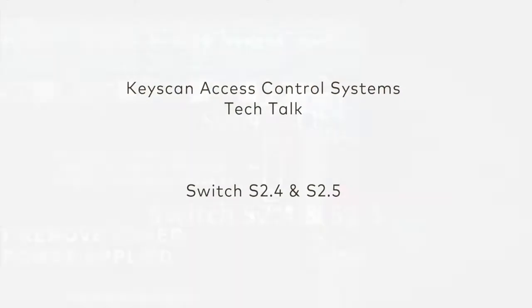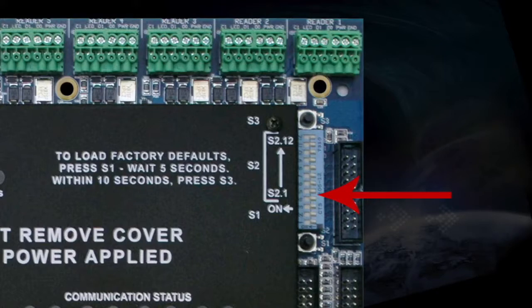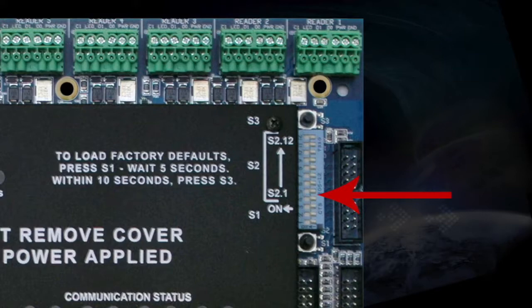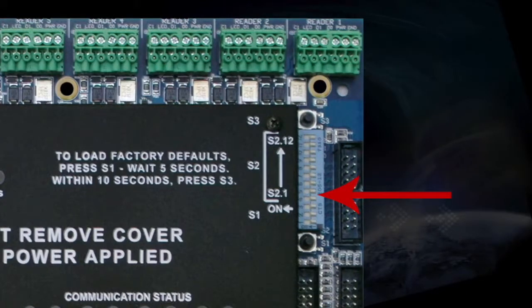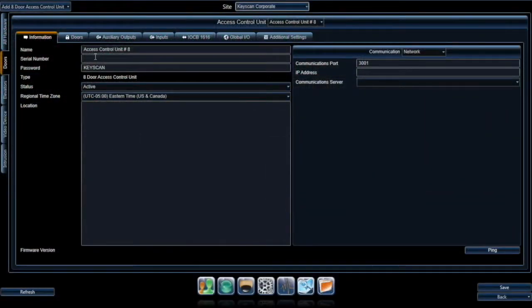Switch 4 and Switch 5 are used to generate an alternate serial number in the event that the serial number already exists within the system's configuration. Note that these switches are not applicable to Keyscan Aurora software — any Aurora-compatible unit will have a 7-character serial number. If you are using System 7 or Vantage software and enter a duplicate serial number, the software will generate a message indicating the serial number already exists and prompt you for options to generate an alternate serial number, which is when you would use these DIP switches.